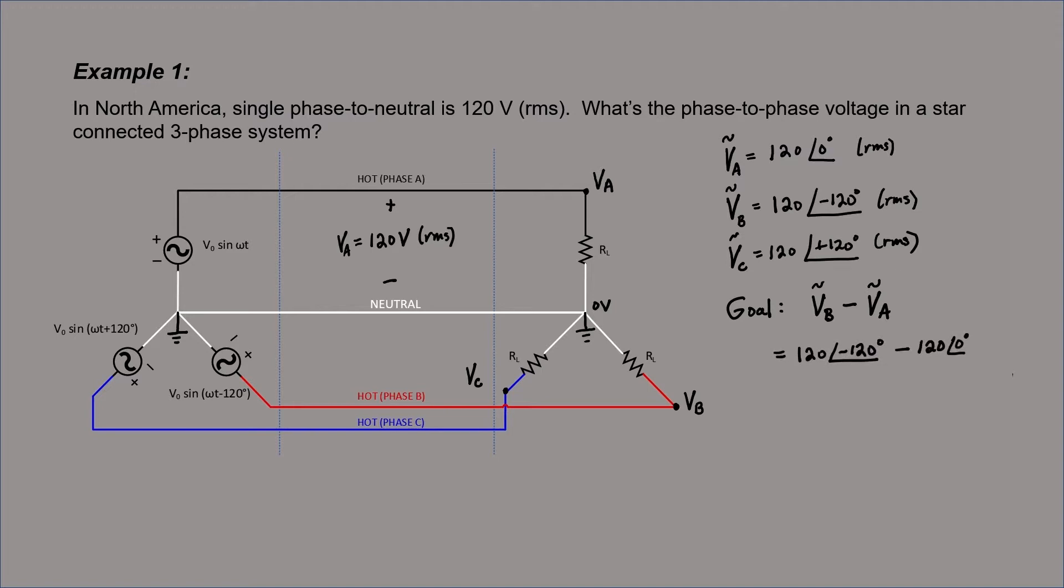First I convert polar to rectangular. Now we can add up the real parts and imaginary parts in order to get a single complex number. If we convert this back into polar form, we find that the magnitude is approximately 208 volts. It means that if I use a voltmeter, set it to the AC mode, put one side on phase A and the other side on phase B, I'll measure 208 volts RMS on the voltmeter.